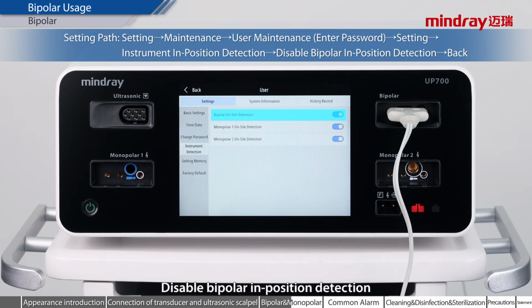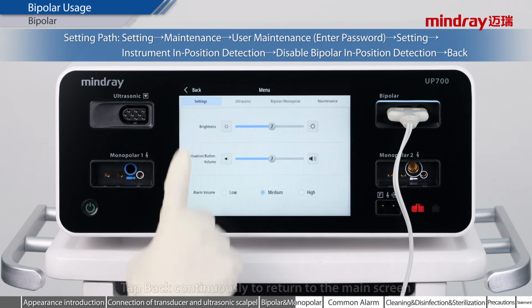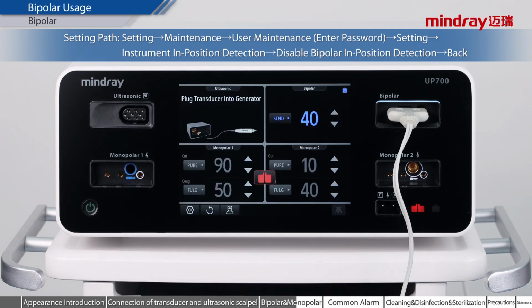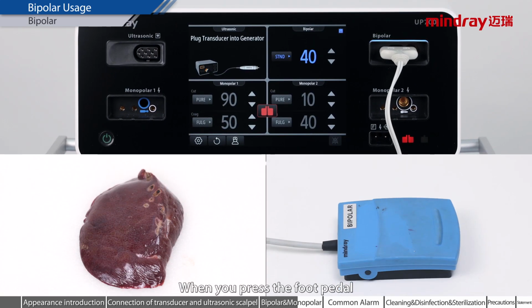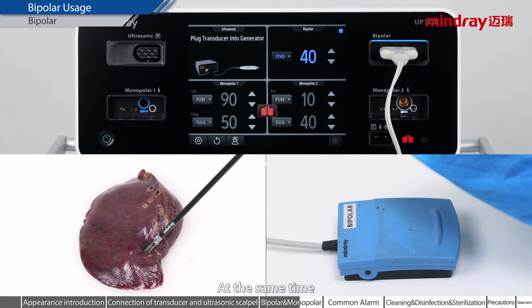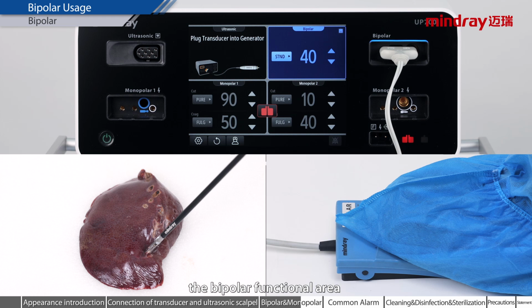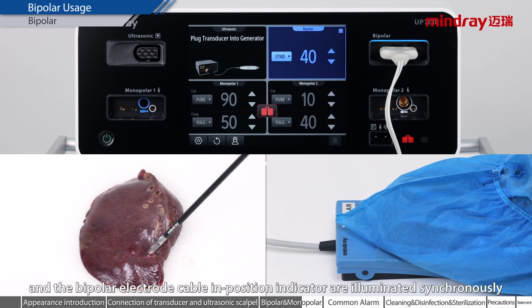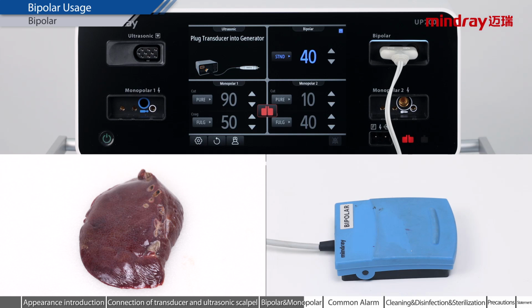Disable bipolar in-position detection. The bipolar indicator is on. Tap back continuously to return to the main screen. When you press the foot pedal, the bipolar energy can be normally output. At the same time, the bipolar functional area and the bipolar electrode cable in-position indicator are illuminated synchronously.